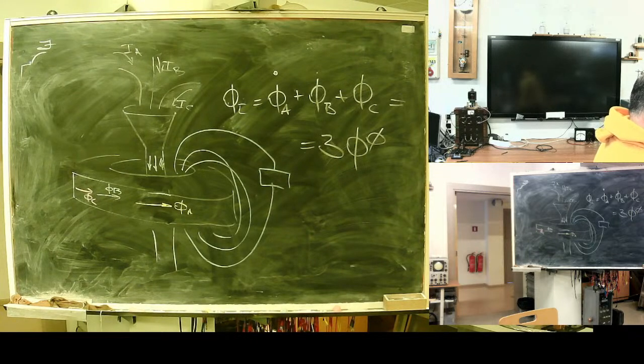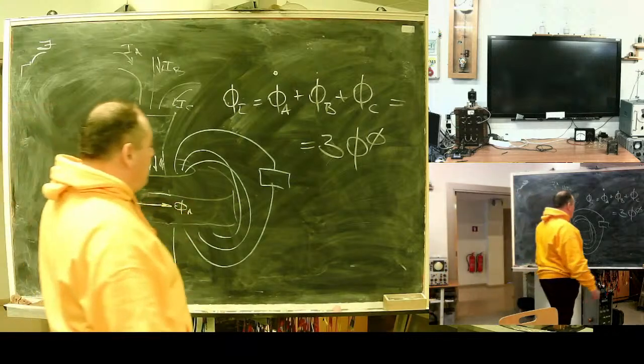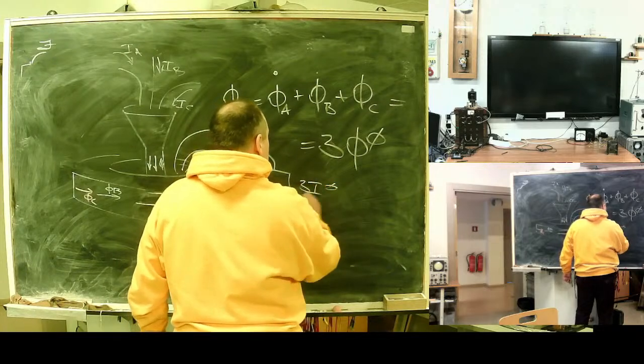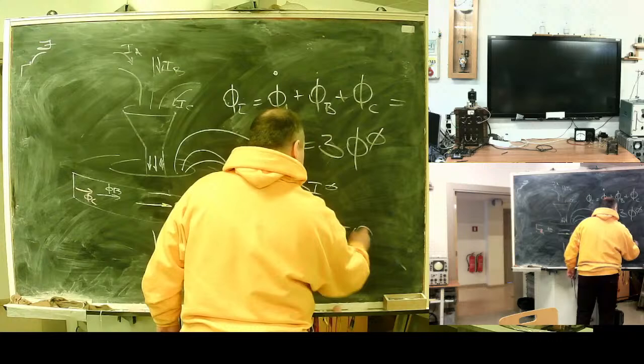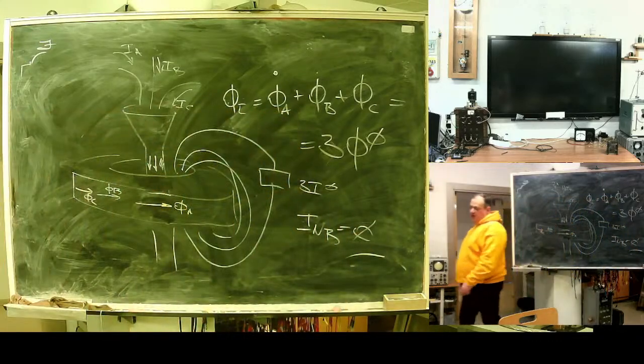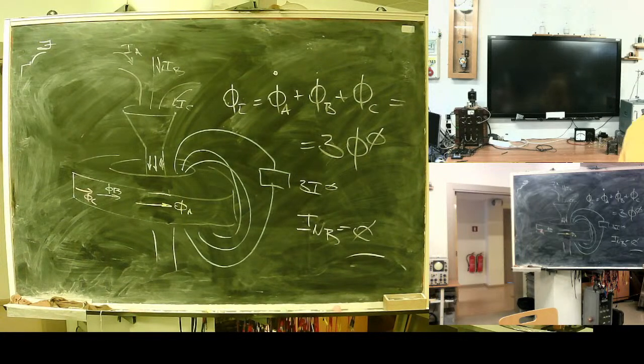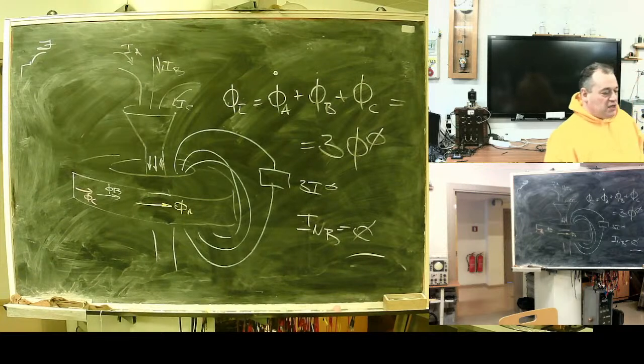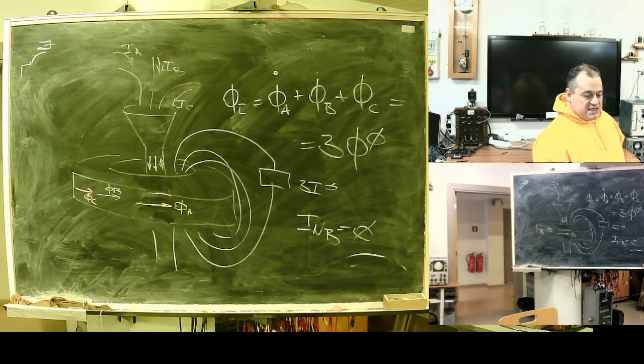Non-balance is a result of core nonlinearity. Non-linearity is between ampere turns and induction. Here everything is uniform. This transformer may have bigger error than phase, but it will not have non-balanced current. Triple flux, and here non-balanced current from transformers is expected 0. There still will be some current because the network itself is not symmetrical. Capacitance against ground is not uniform, but it's much smaller. You will get your sensitivity.